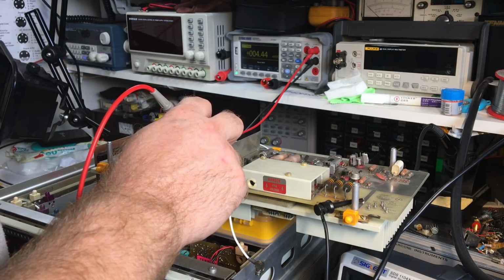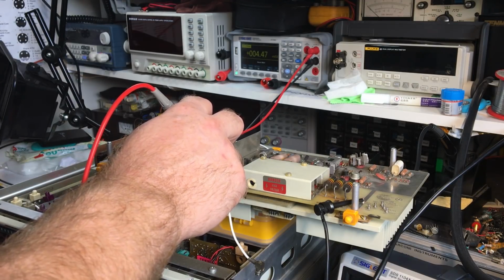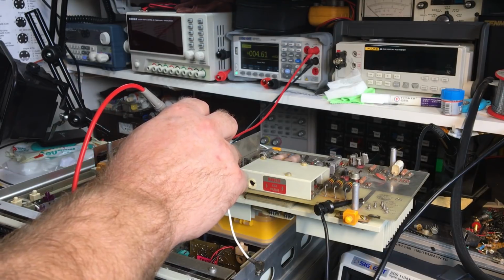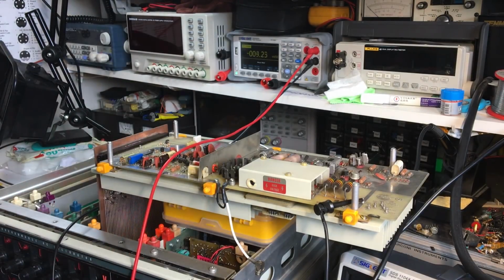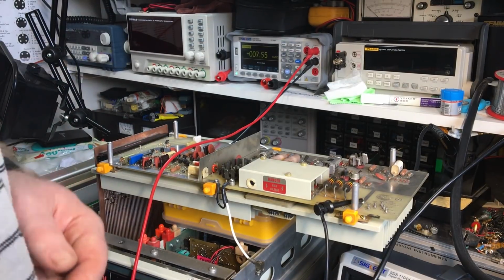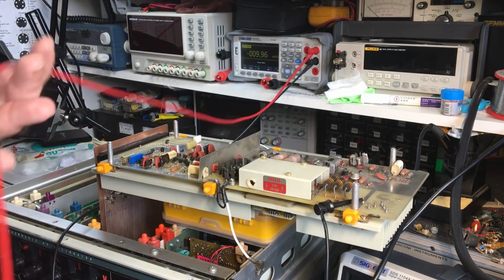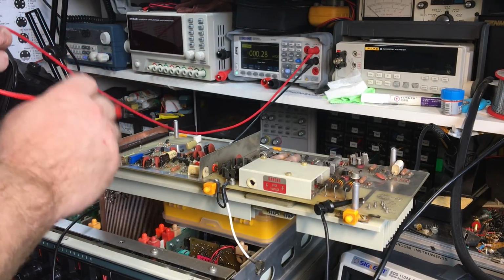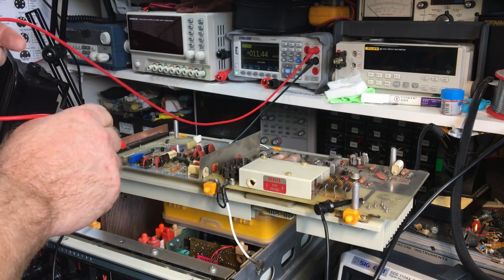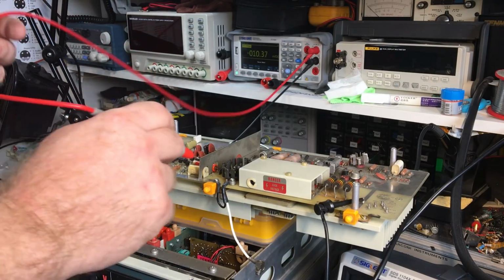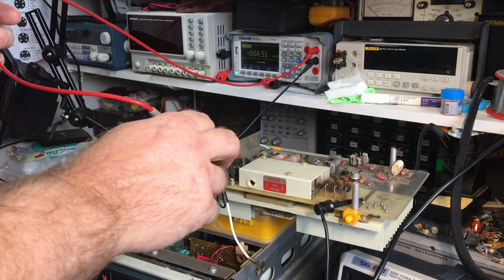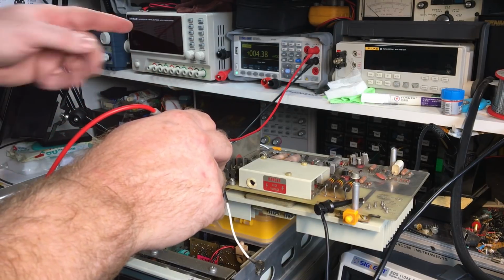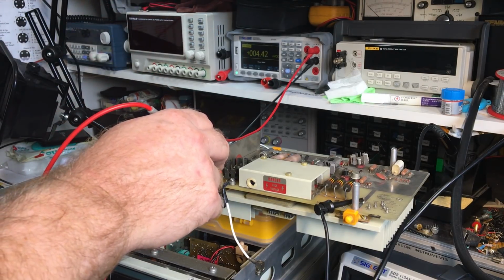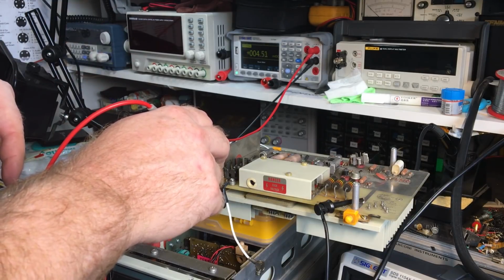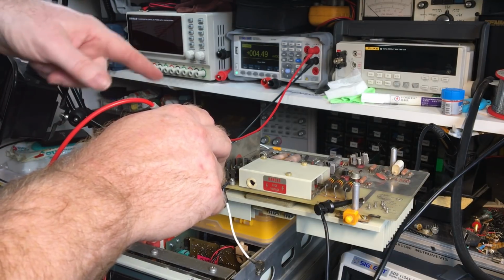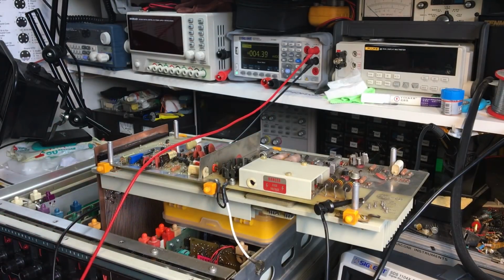So 0 plus or minus 100 microvolts. Well, yeah, it's not got that, is it? So I need to look into that part of it. So that's the first thing which hasn't quite gone to plan so far. The manual says to adjust R6 here, which is something I already did, but in the setup I forgot to mention it. You have to wind this all the way counterclockwise, and that's where it is right now. If I then wind it clockwise, the offset is going up in value. So it cannot actually be reduced any further. So that could be an issue in this part of the circuit here. So I need to look into that, because it does seem like there's an issue there.